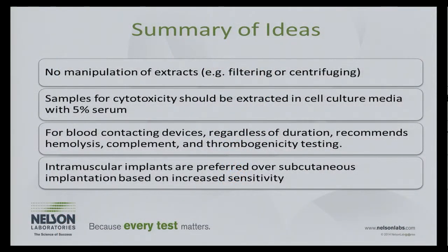We cannot manipulate the extracts. Okay, so we can't centrifuge, we can't filter, and this is hard when we have devices that may shed particulates, especially when we cut them up into pieces like we do when we extract them. So just keep that in mind. We can't, or if we do manipulate it, we have to justify why it's appropriate.